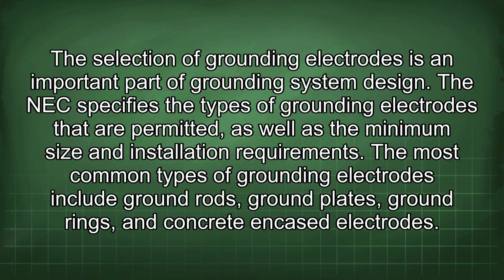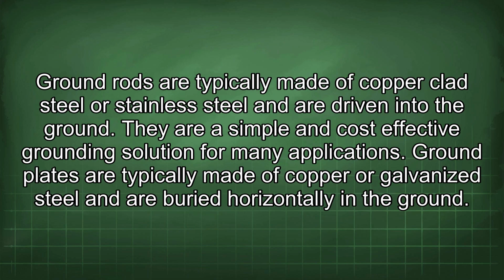The selection of grounding electrodes is an important part of grounding system design. The NEC specifies the types of grounding electrodes that are permitted, as well as the minimum size and installation requirements. The most common types of grounding electrodes include ground rods, ground plates, ground rings, and concrete encased electrodes. Ground rods are typically made of copper-clad steel or stainless steel and are driven into the ground. They are a simple and cost-effective grounding solution for many applications.